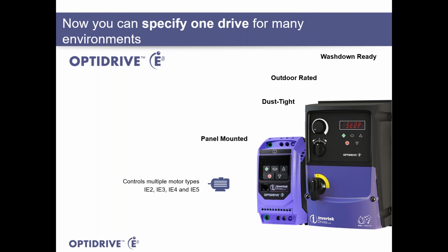Now, in the E3 family, we have the IP66, so washdown ready for things like food and beverage, but it's also outdoor rated, which means that the case of the drive is actually UV stabilized. So it's dust tight, so we can use it just about anywhere. The only thing I do suggest is not to put it in direct sunlight, not because of the UV issues, but because of the heating. So put it in the shade. Or we have the IP20 drives, which go into control panels.